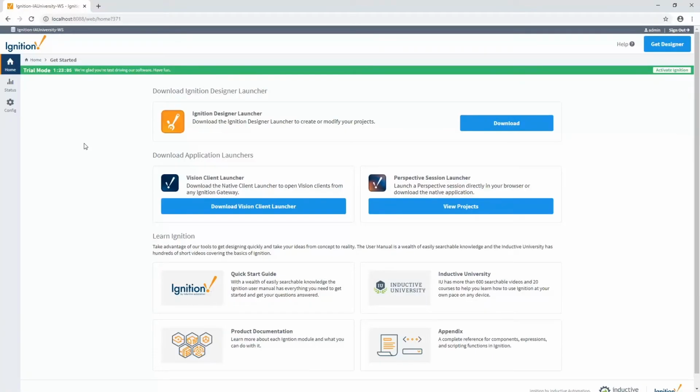In this session, we're going to install and configure the MQTT engine module for Ignition. The engine module allows us to connect to an MQTT server and subscribe to data. Engine will automatically discover all the data that's there and turn them into usable tags in Ignition that we can add configuration to, like history or alarming, or we can simply use on our screens.